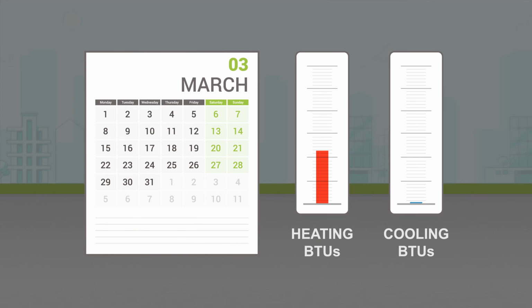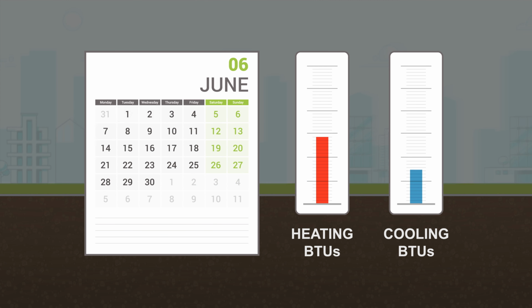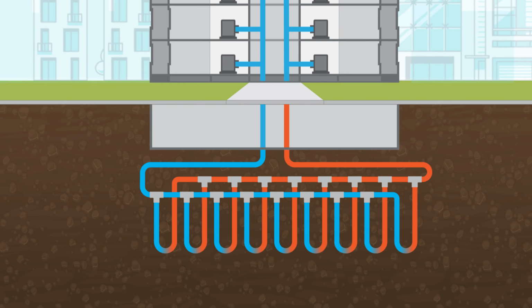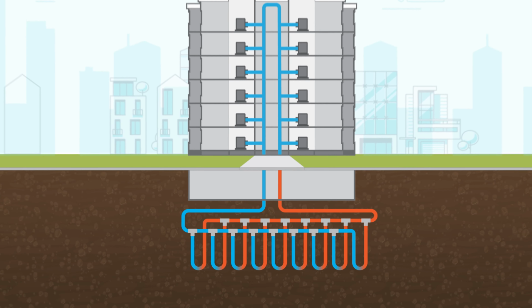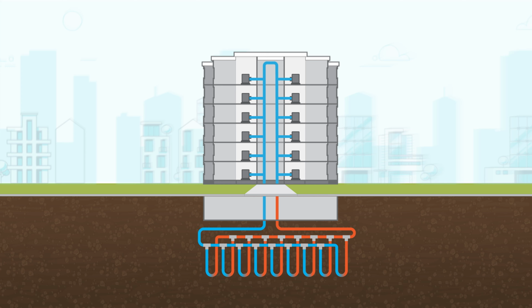The proper way to design a geothermal borefield is to accommodate the building's annual heating and cooling needs, not just the peak. Once the borefield is designed and installed properly, you're only halfway there. It still needs to perform long term.